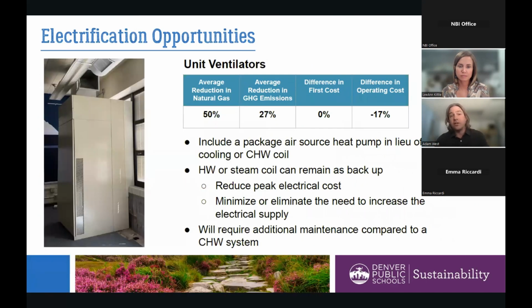For unit ventilators, we're putting in a lot of new vertical unit ventilators. Many schools have the old low horizontal unit ventilators that teachers often stack things on. We're moving towards vertical unit ventilators that have more room and can fit a heat pump. Again, these have the same DX cooling already in place—essentially you just add a reversing valve and controls.